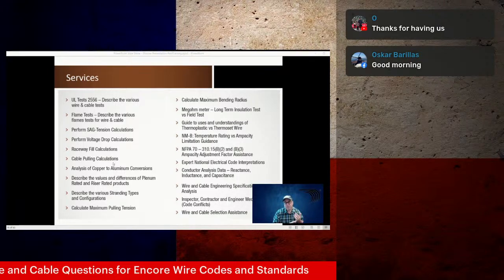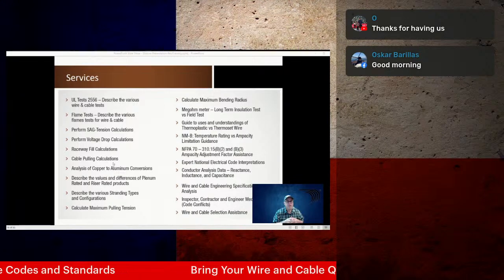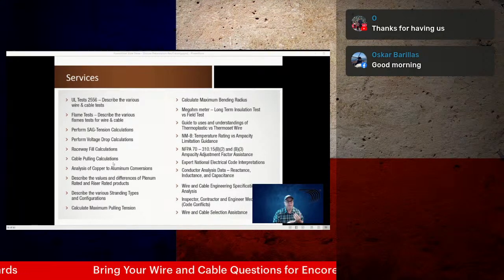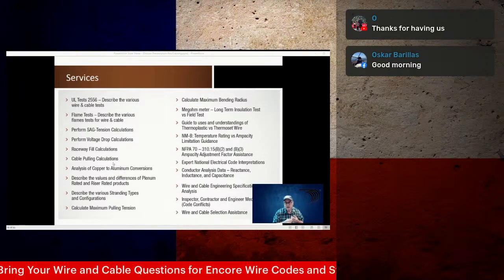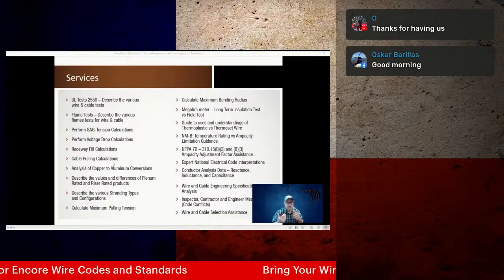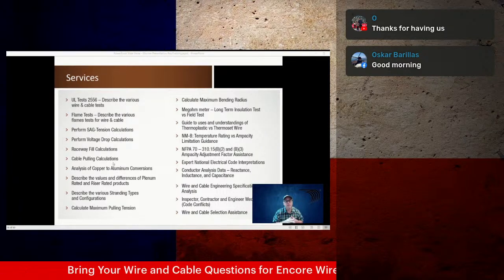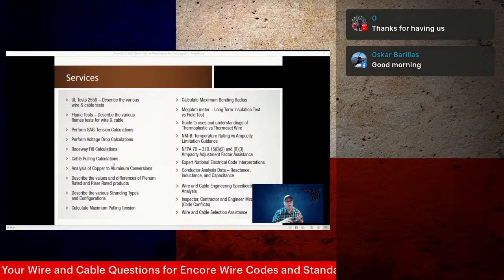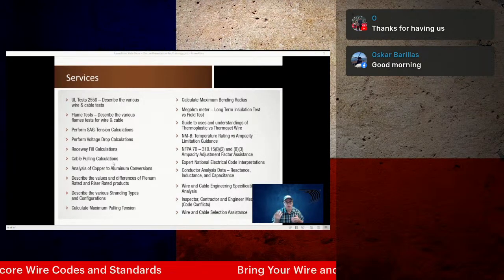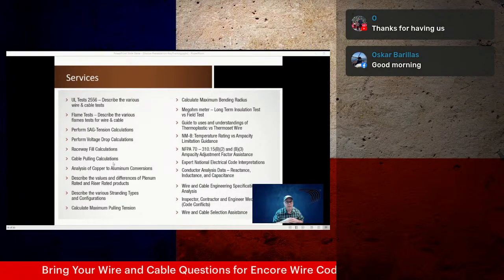We explain the aspects of 2556, which is the different testing standards for wire and cable. We can do training on flame tests, explain what it means, VW-1, all those kinds of things, IEEE 1202, installation in cable trays. We can explain all that. We can perform sag tension calculations, typically only for service drops, or if you're using our 1350 for aerial applications, typically when you get into that.